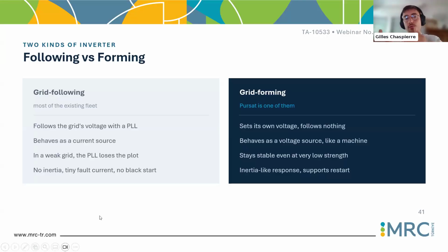So of course, we are moving progressively to more and more grid forming converters if, of course, the technology is mature enough. And I just want to highlight that the Pursat battery in Cambodia is grid forming, so you are already there. And this grid forming aspect is entering progressively into the grid code, which is very important, because if you are not making it mandatory through a clear grid code or technical requirement, no developers will invest in this grid forming technology. So you need to have either incentives or clear technical requirements to make sure new developers come with grid forming technology.